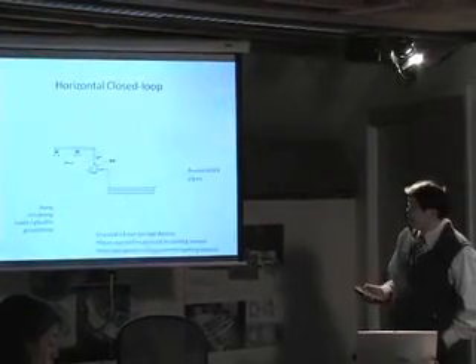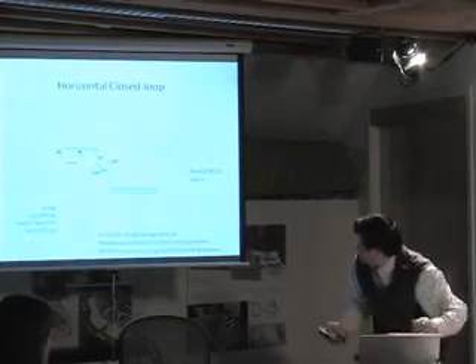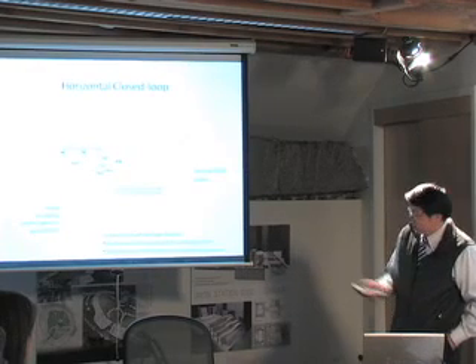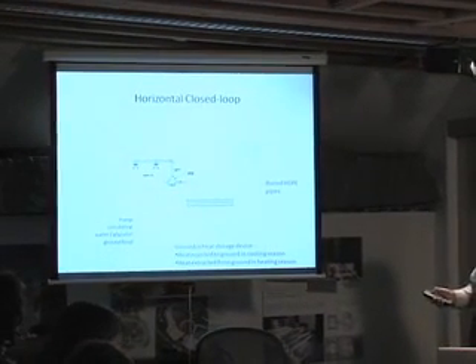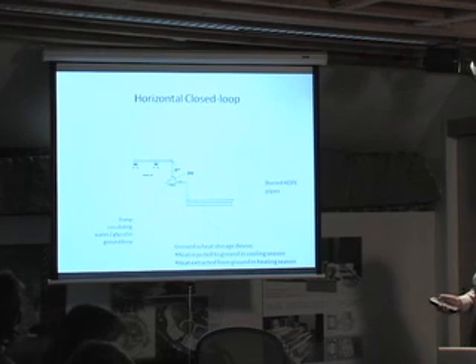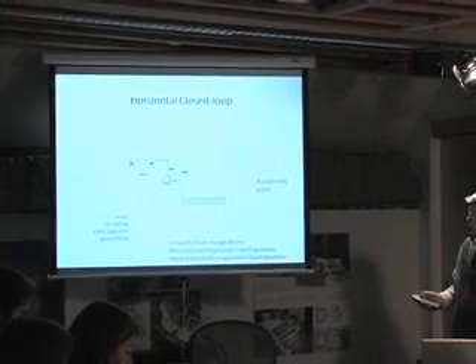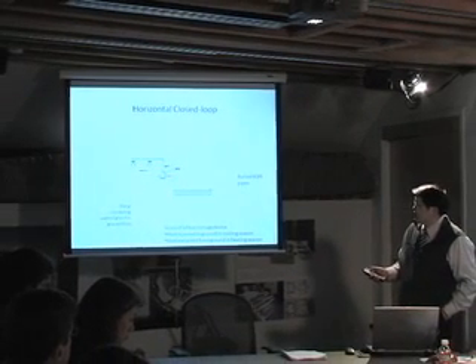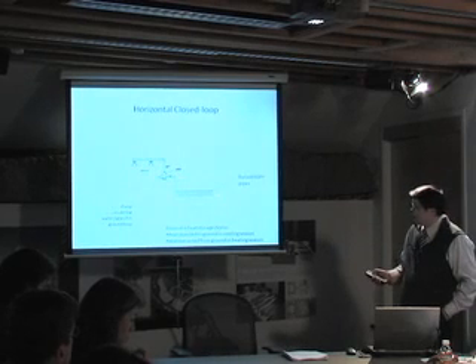The different configurations for geothermal heat pump systems. This picture shows, I don't know why it's not showing up the ground. Well, on my computer there's a line here that shows the grade level, and you have the heat pump in the mechanical room. This is the building here, and then you have buried horizontal plastic pipes, the HDPE pipes, high density polyethylene pipe. You bury it horizontally, usually below 6 feet, and then you fill the ground loop with a glycol water solution, and then you pump the water around and through the heat pump to take the heat away from the heat pump or take heat from the ground to the heat pump.